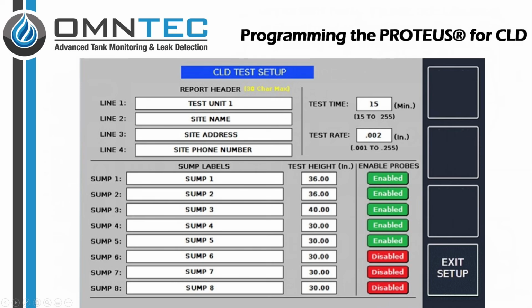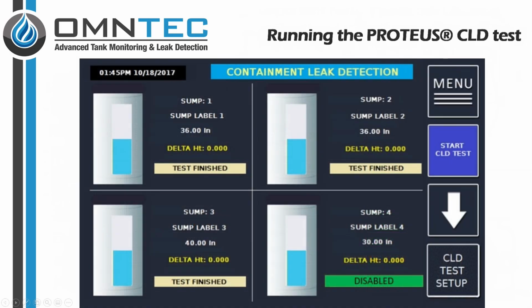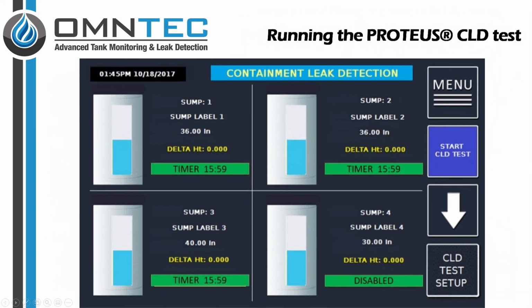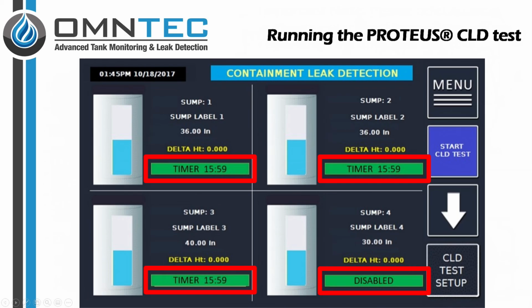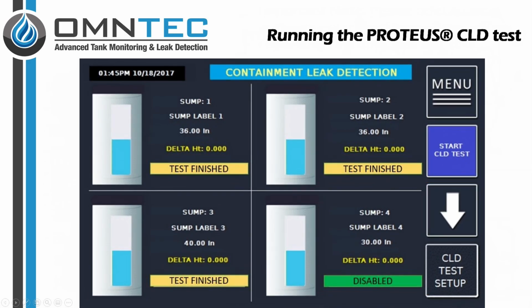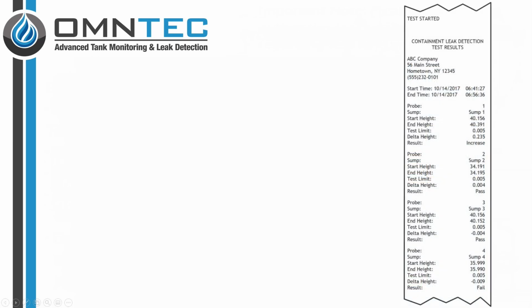Now, let's run the test. This screen will show the current programming and enabled probes on the CLD tester. To begin a containment leak test, press the Start CLD Test button. A timer will appear for each enabled tank. Once the timer runs out, the message will read, "Test finished." A report will print out.